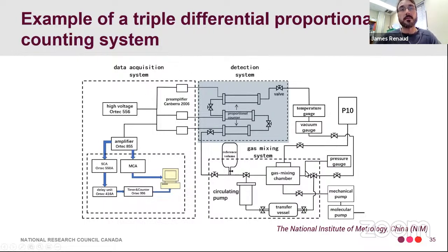The end goal of this whole system is to determine the activity concentration of the gas inside your system. It's also to produce the CRM. So there's going to be a portion of the gas handling system that contains the same gas that's being measured, so that it can then be removed and serve as a CRM for whatever purpose. But the gas contained in that transfer vessel is then well characterized. That's the whole idea.